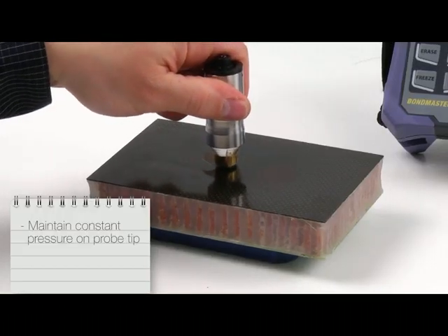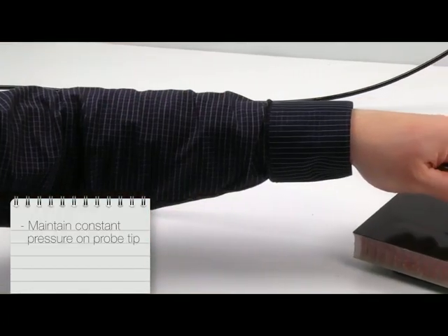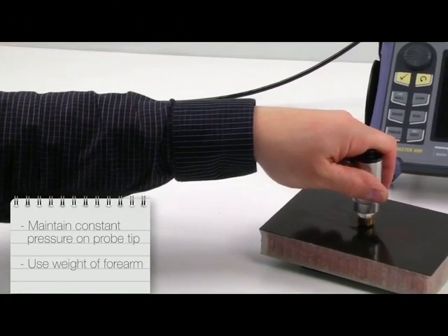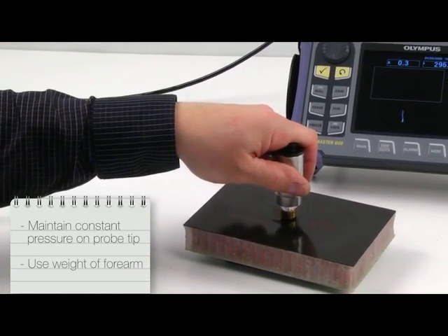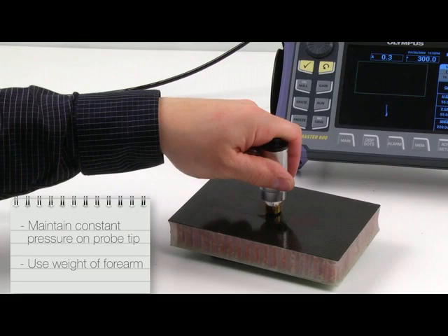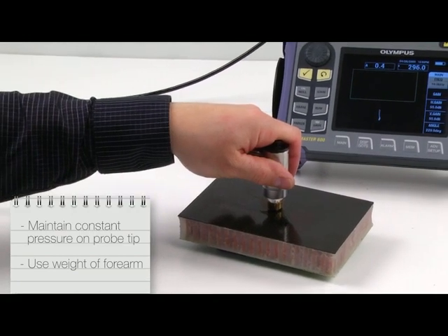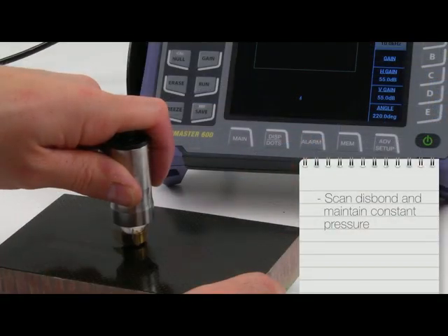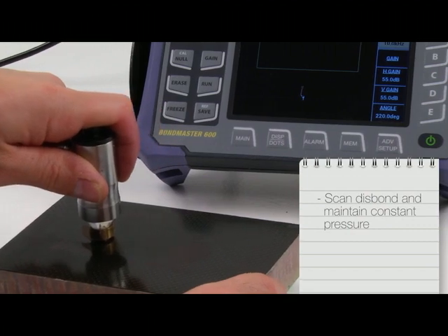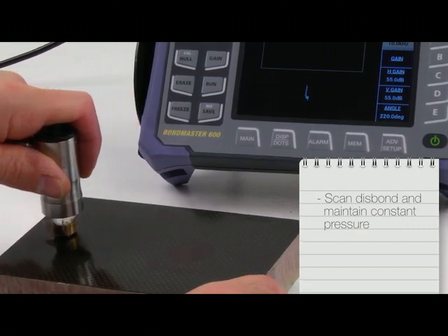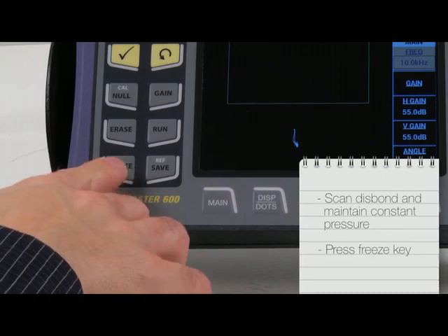Maintain a constant pressure on the probe tip. One easy way to keep the pressure constant is to use the weight of your forearm to press the probe against the surface. This helps ensure constant pressure and minimal effort. Slowly scan over the simulated disbond while maintaining constant pressure. When done, press the freeze key.